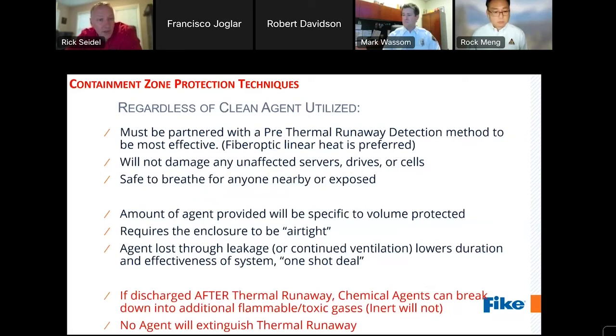Regardless of the clean agent that is utilized, it must be partnered with a pre-thermal runaway detection method to be the most effective. And the fiber optic linear heat detection system is the preferred and most effective type of system to activate a clean agent system. It will keep you ahead of the thermal runaway. It will not damage any unaffected servers, drives, or cells. And clean agents, one of their primary benefits is that they are safe to breathe for anyone nearby or who may be exposed to the gas.